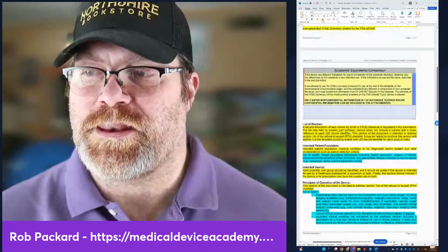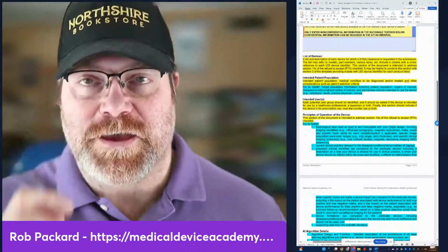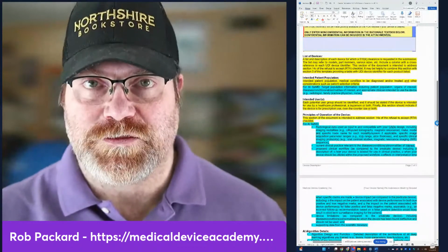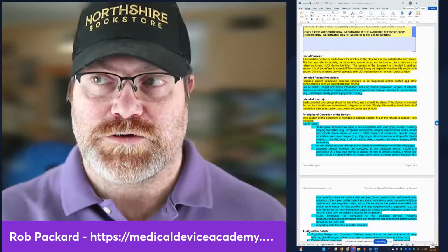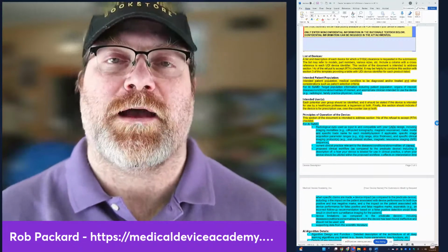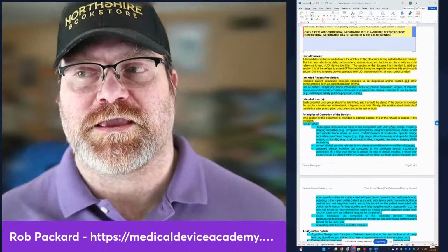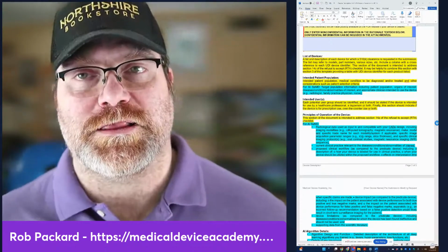As we go down, the next thing we have is a list of devices. For the list of devices, if you only have one device you're submitting, the list is one. So you just say the only device in this submission is this. That's it. If you have multiple sizes, each one should be listed. If you have different configurations and variations, you're going to list those.